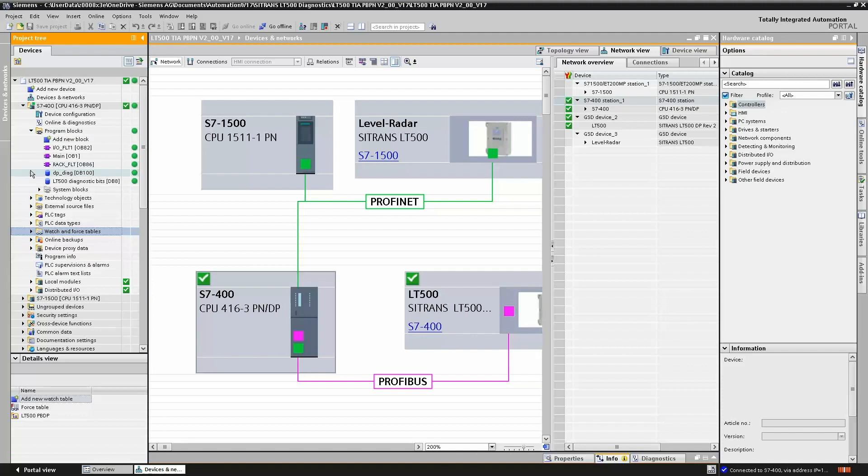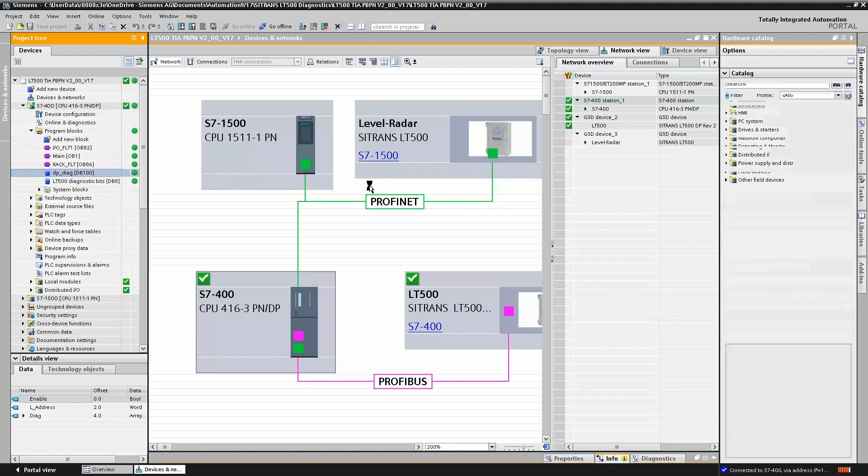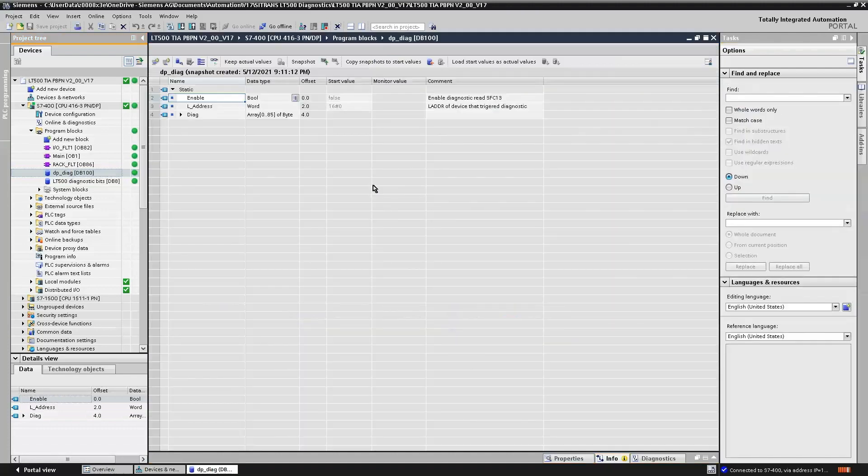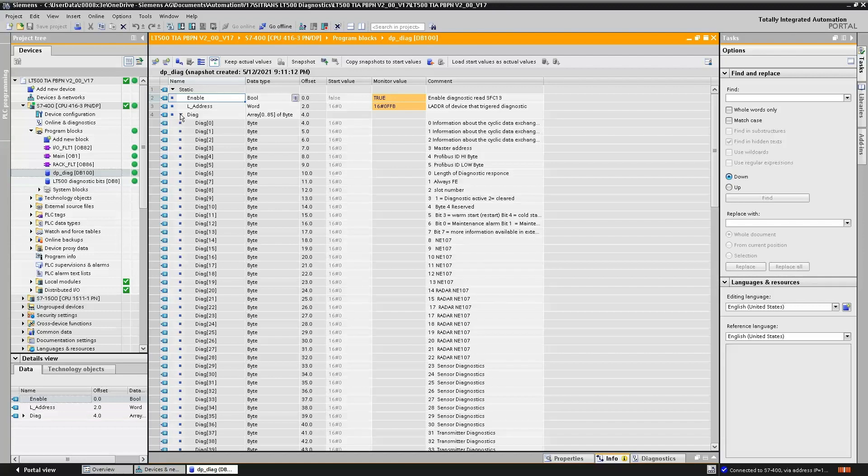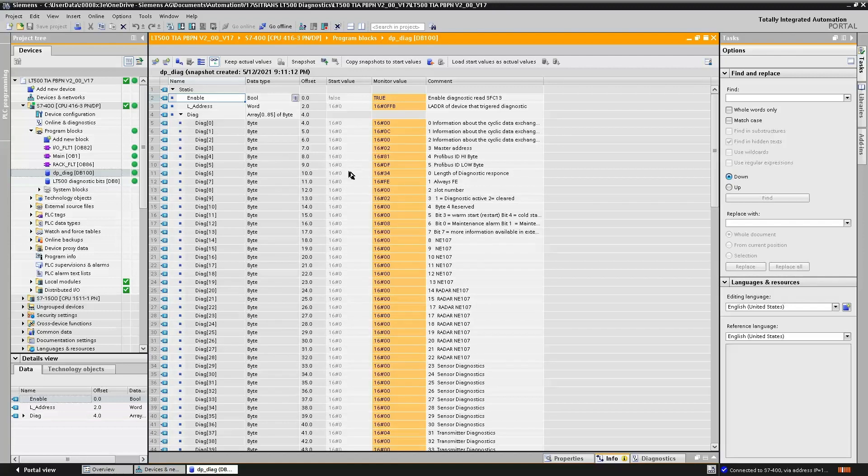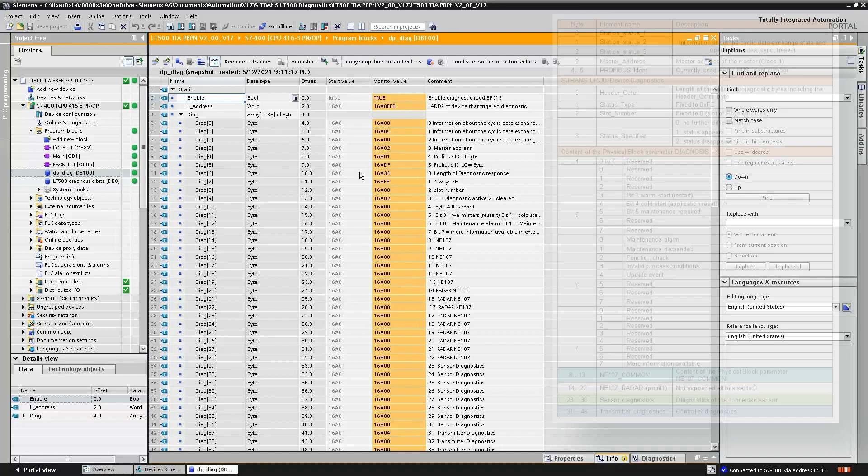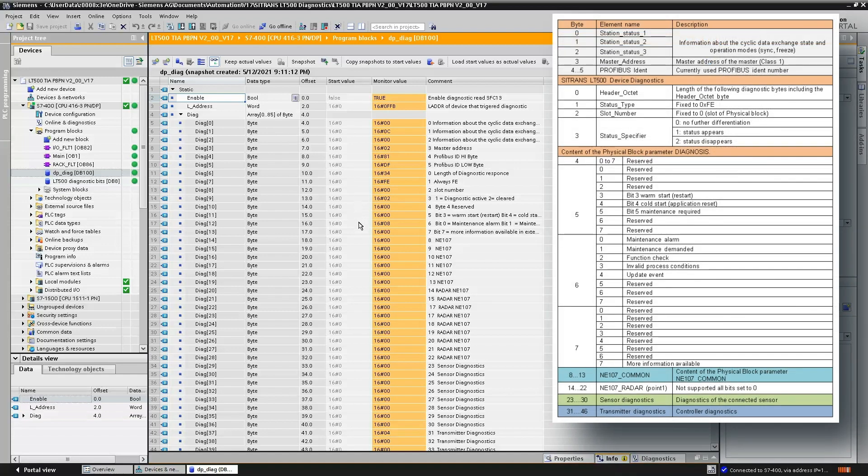Let's have a look at our data block which we have set up to capture the diagnostic information from the Sitrans LT500. If we go online to our data block and look at that event that occurred, we can see now that we do indeed have a diagnostic message which has been captured by the S7-400.